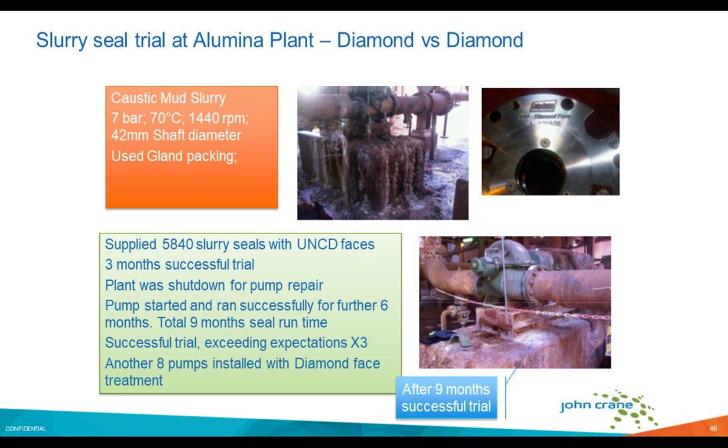And you can see after 9 months, this is the same pump in the bottom right here. A much different story in terms of the leakage and the condition of the base plate around the pump.